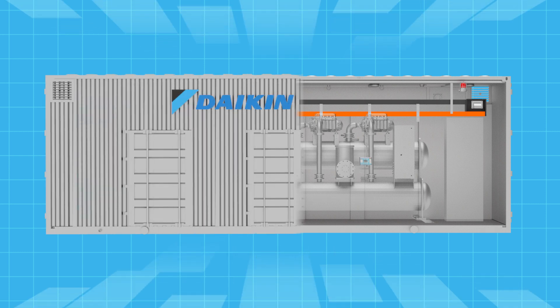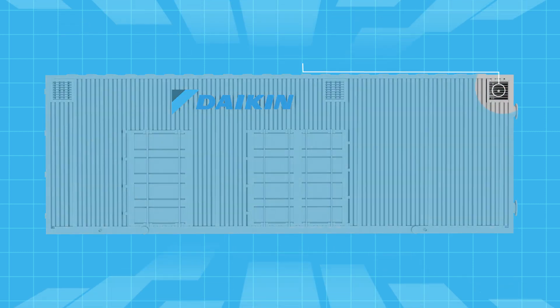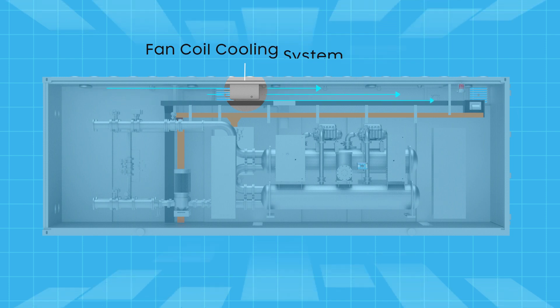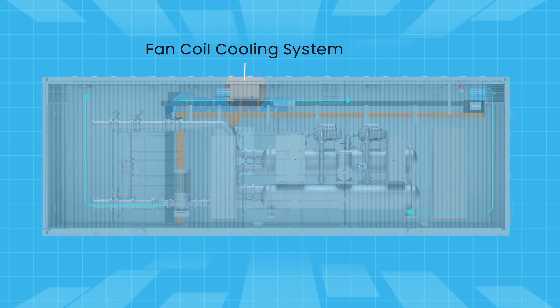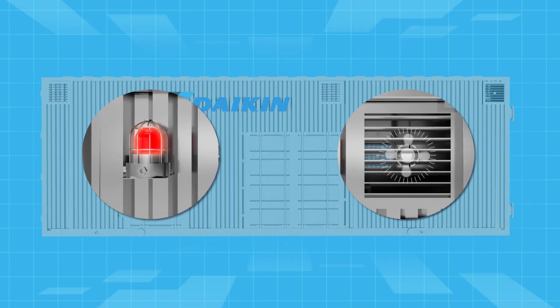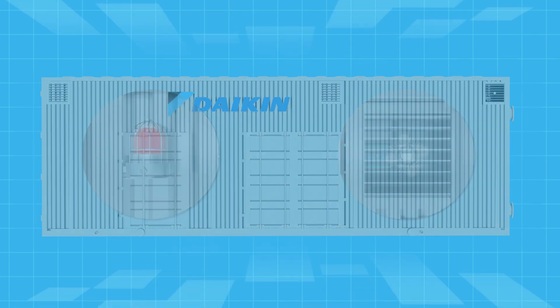Because safety is our top priority, our safety components include the exhaust fan, built-in detectors for water and refrigerant leaks, and a fan coil cooling system to control ambient temperature. If a refrigerant leak is detected, it will activate the exhaust fan to draw in fresh air and exhaust out the refrigerant.